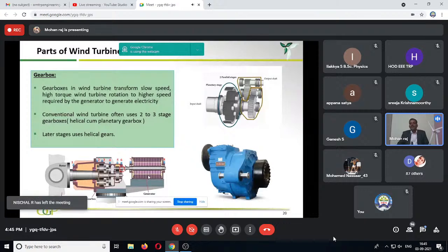We could not connect directly to the rotor shaft because the speed of the blade is between 10 to 30 meters per second. Depending upon the capacity, it will vary. If it is higher capacity, the RPM is very low. So to convert the slow speed, high torque to the 1500 RPM, for that purpose only we are using the gearbox. Okay, so 80% of the wind turbines available in the market are geared wind turbines.